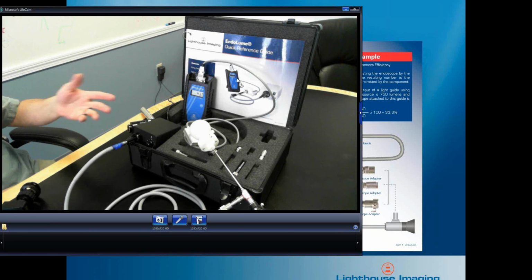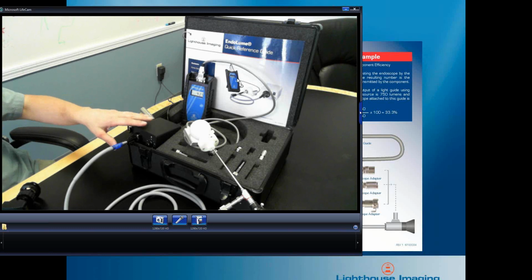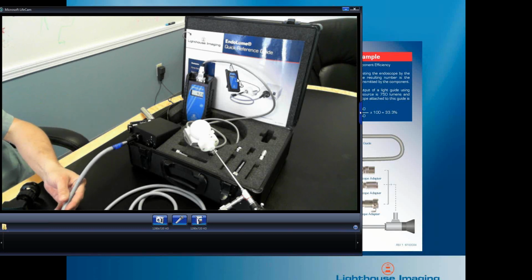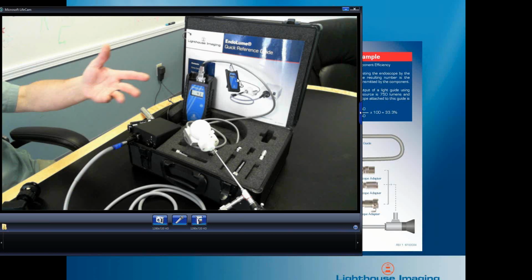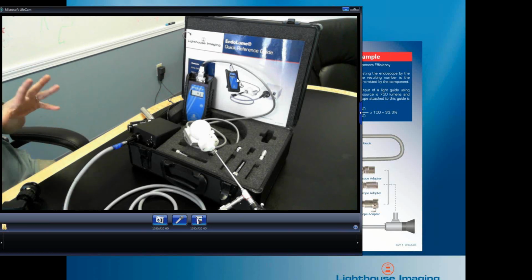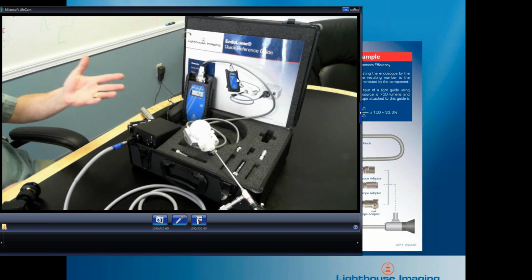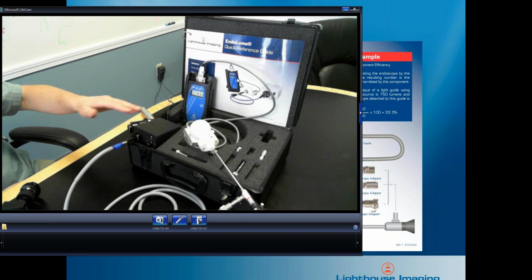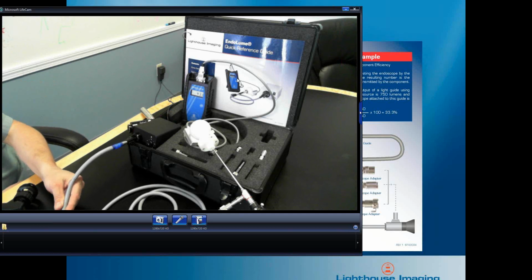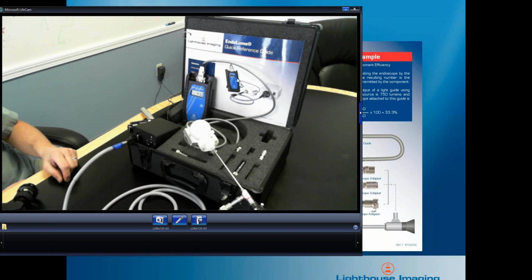So if you had a complaint from the surgical theater of poor quality or dim image, you test the light bulb, maybe it was on the low side, maybe the cable had some breakage in fibers a little bit, and maybe the scope was a little bit weak. So all of those things together make a bad image. You'd have to kind of go through the whole system at that point. Much more common, though, would be maybe the bulb needs to be replaced, maybe the cable has some broken fibers, or maybe the scope has some sort of an issue and should be sent out for repair. With the EndoLume, you've identified uniquely which one of those components is the problem area. Excellent.